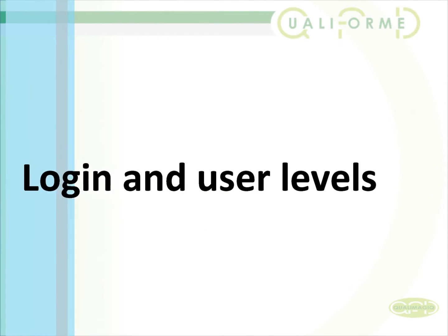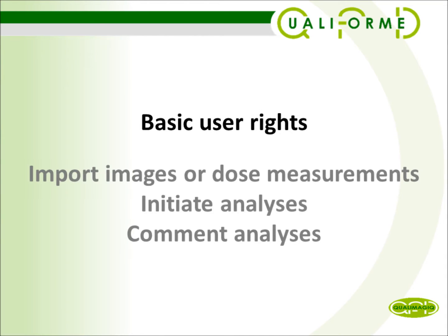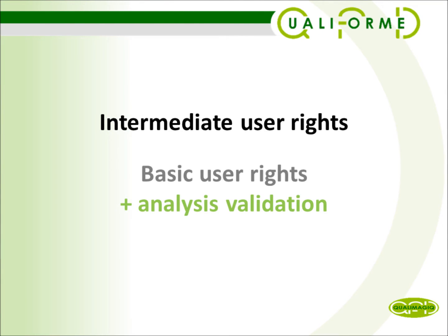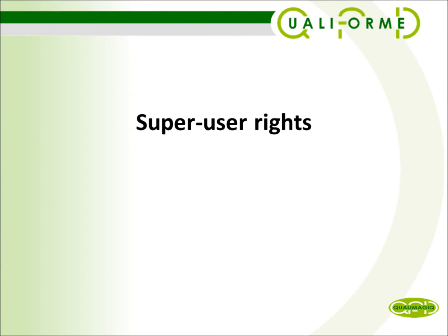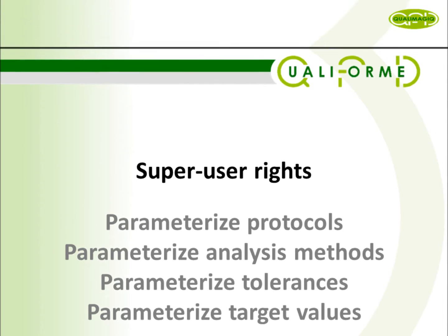Login and user levels. When you boot up the program, each user needs to log in. QualiMagiQ acknowledges several user levels, each with differing rights. Users with basic rights can import images and dose measurements, initiate analysis, and comment on them. In addition to enjoying basic user rights, intermediate users can also validate or reject an analysis. This would be the appropriate level for a technician whom you would like to assign responsibility for approval of analysis, for example. You may delegate one or more super users authorized to parameterize protocols, analysis methods, target values, and tolerances.